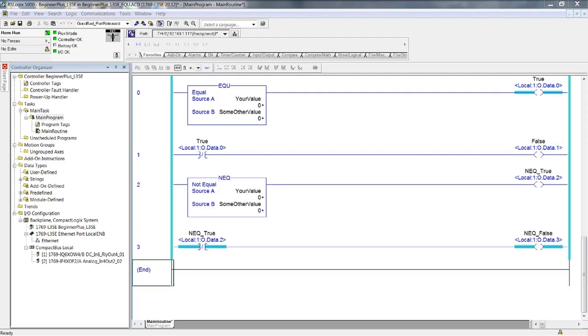Continuing from the previous project with the equal instruction, we had you add two more rungs of logic matching the first two but with the not-equal instruction — a rung condition true out for the not-equal true, and a not-equal false output. Now we have two instructions both using the exact same two values, so you can easily compare the behavior of the equal and not-equal instructions based on the four outputs on your digital field device simulator.